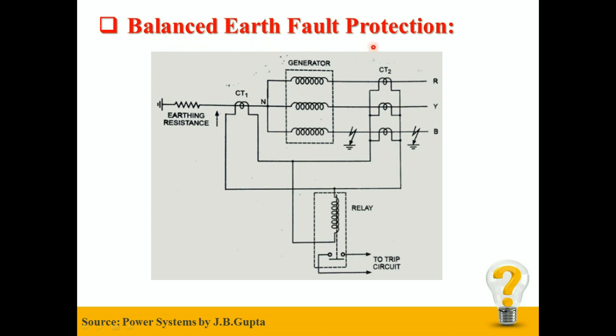Balanced Earth Fault Protection: The schematic arrangement of a balanced earth fault protection for a three-phase generator is shown in the figure. In this scheme, three line CTs — one mounted in each phase — have their secondaries connected in parallel with that of a CT mounted on the conductor joining the star point of the generator to earth through an earthing resistance. The protection is limited to the region between the neutral and the line CTs, and provides protection only in case of an earth fault, not in case of an external fault.